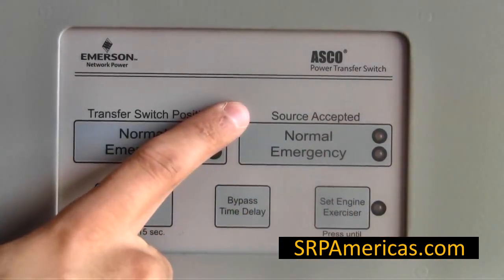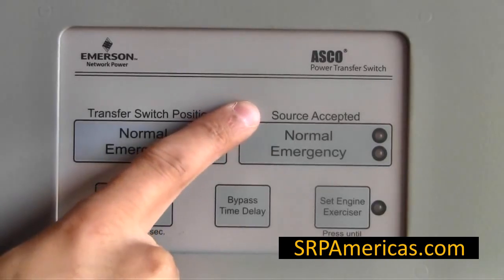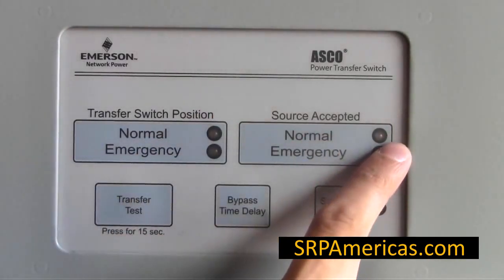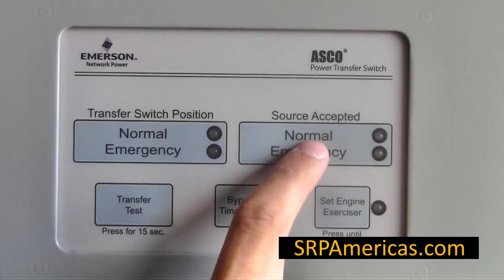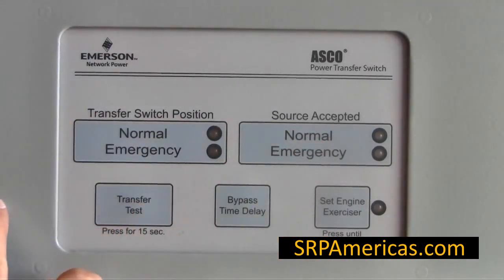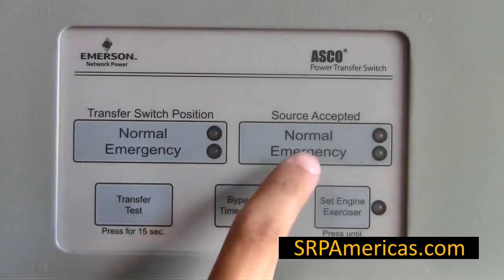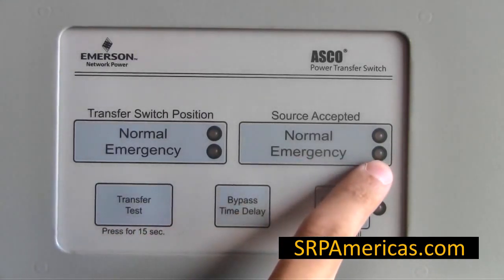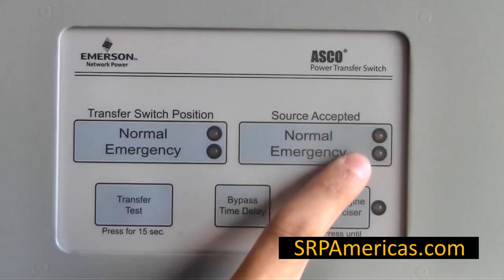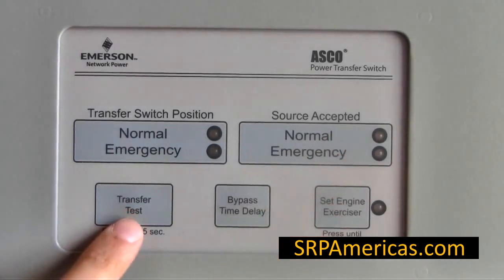The right section indicates what sources are available. If the light is illuminated, the normal source is within tolerance levels of the parameter set for the transfer switch. The same goes for the emergency button. It is possible that both lights are illuminated at the same time.